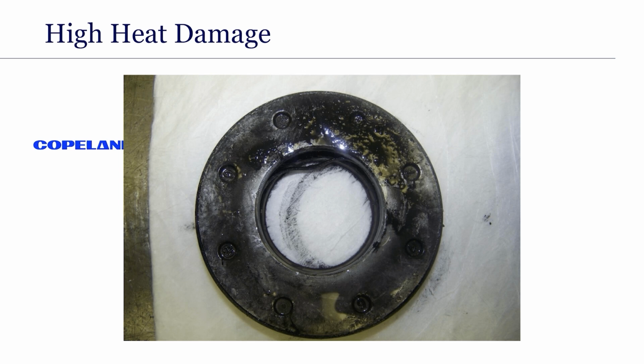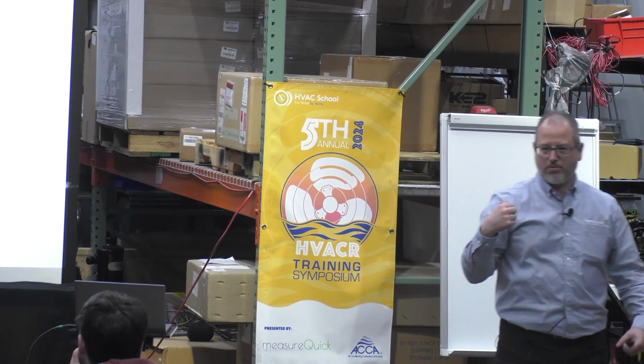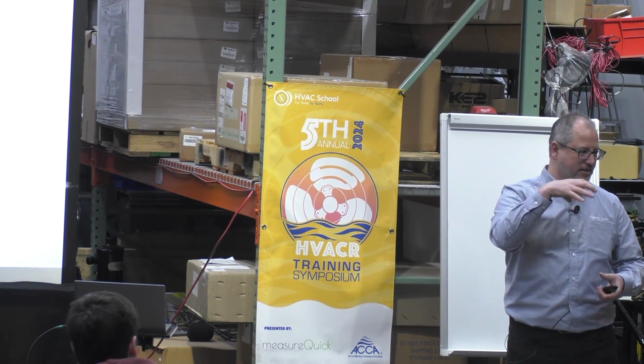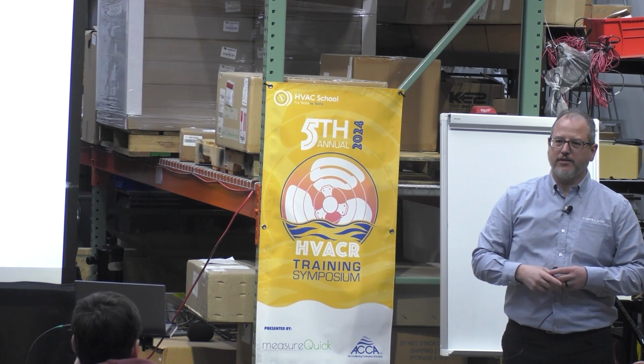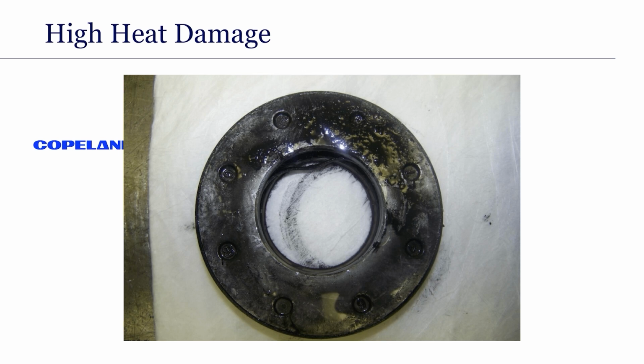If you remember what our floating seal looked like before, if you see one that looks like this, that is not good. It's a little hard to see in here, but this is what's supposed to be green, and you can see it's ripped here. This floating seal has come off balance, so that pressure differential in that system has gone too far. So obviously you can see it's had a lot of problems.